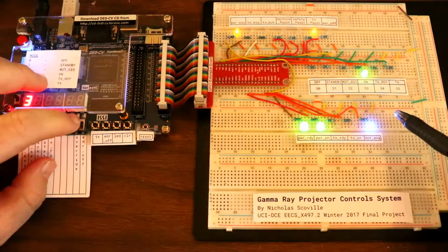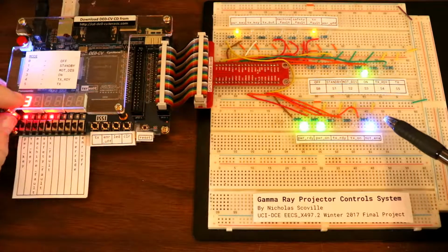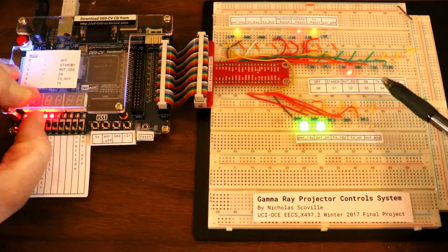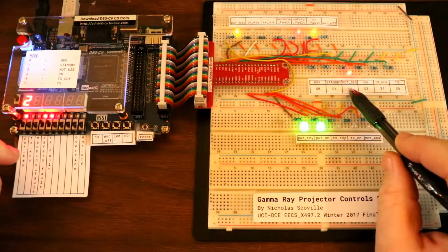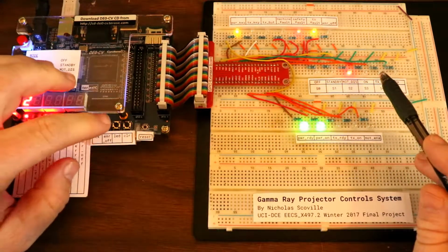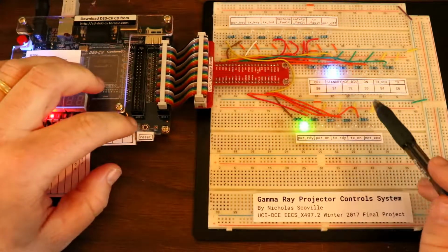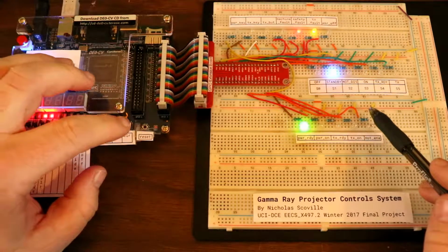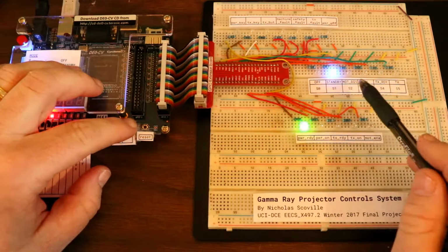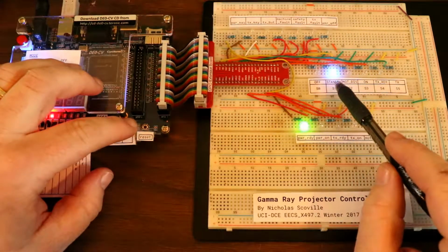I also have an override button. So let's say I had a safety fault that drops me back to motor disabled. I can actually click the clear button and it will clear the faults, and we'll drop back to standby because we don't have the transmit fault any longer.